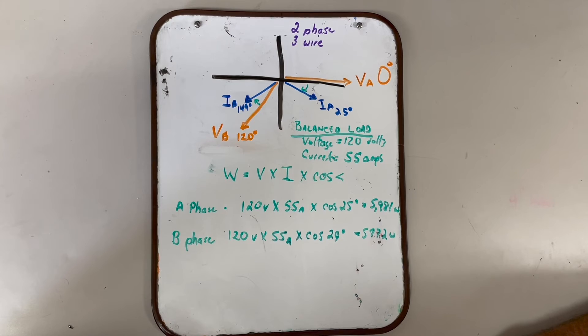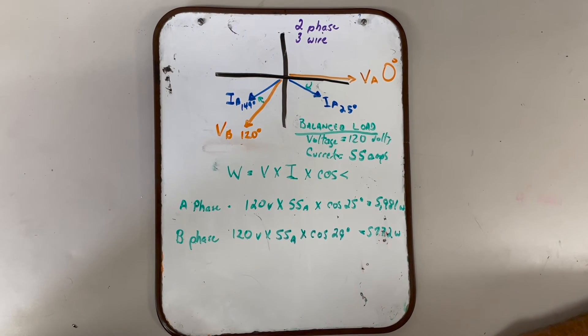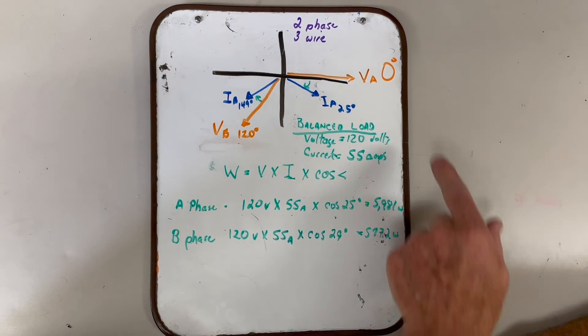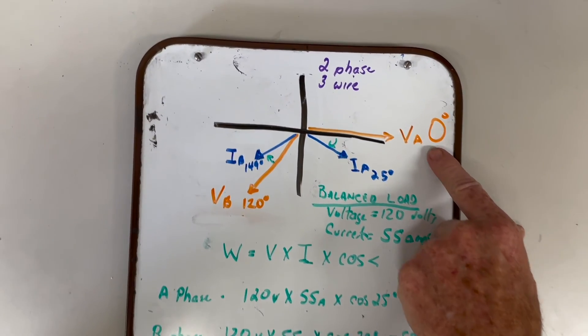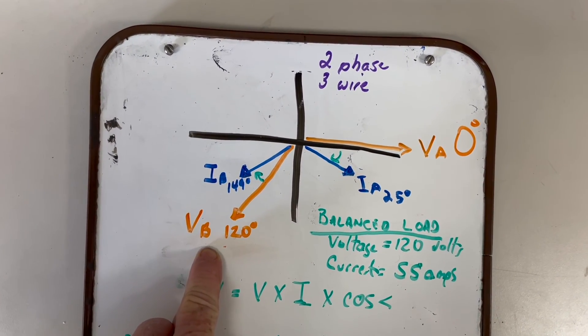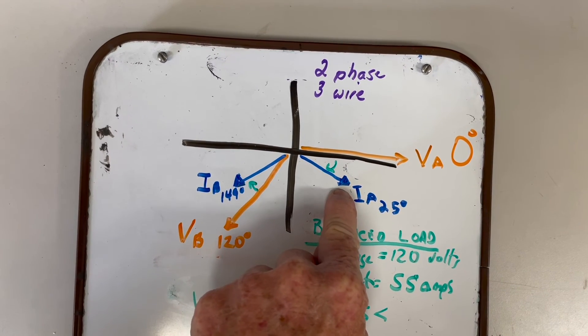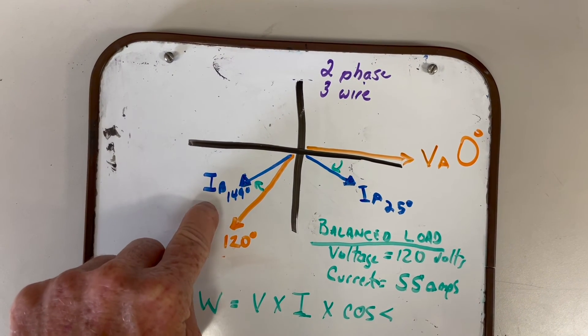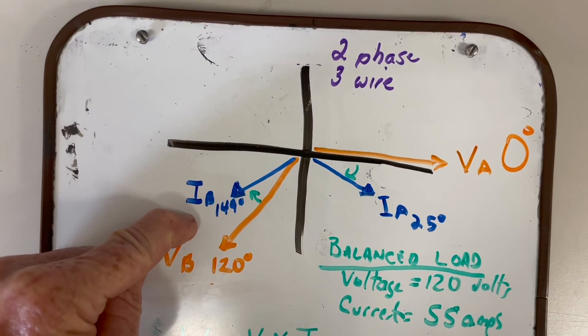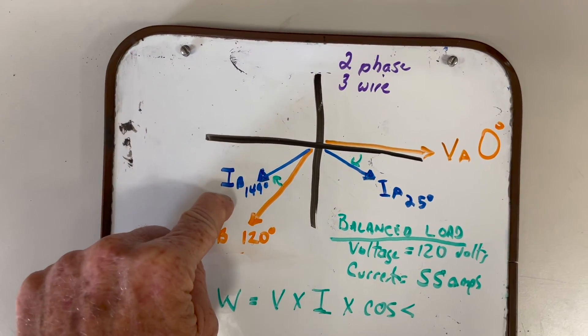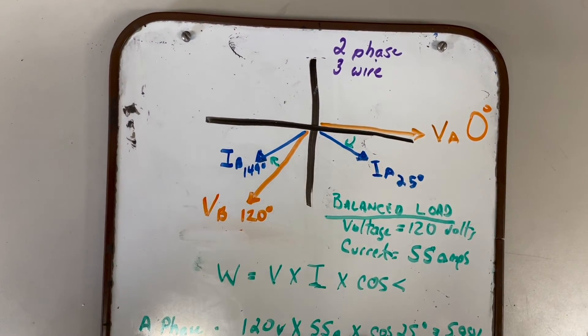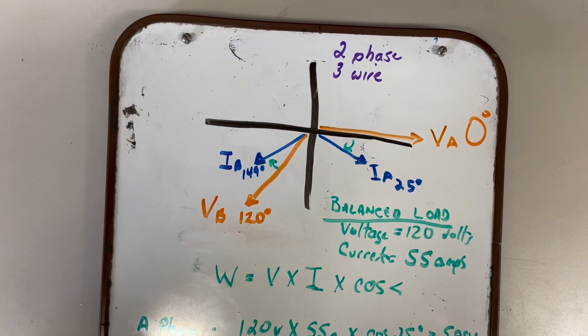Two phase three wire vector diagram, just to show you in case someone ever has to add up the watts. What we're looking at here on two phase three wire: we have voltage A at zero degrees, voltage B at 120 degrees. We have current A lagging voltage A by 25 degrees. We have current B lagging voltage B by 29 degrees.